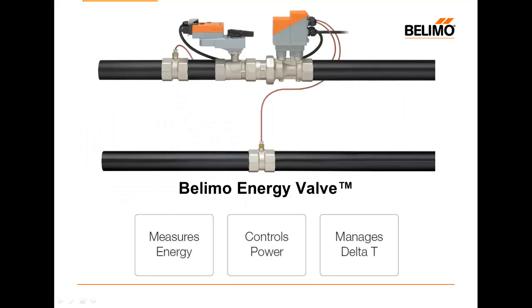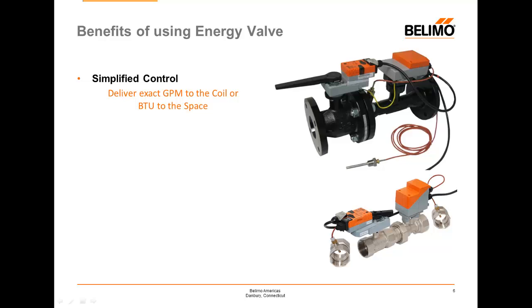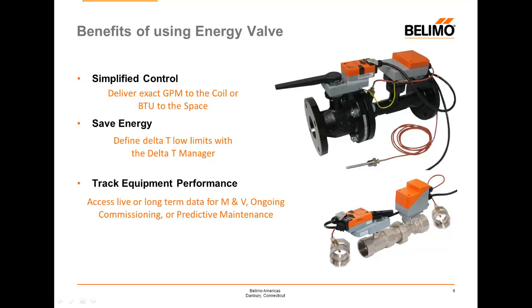Let's go ahead and talk about the Belimo energy valve. The Belimo energy valve can do several things: it measures energy, it controls power, and it manages delta T. The Belimo energy valve is a pressure independent valve with a fully integrated BTU meter. It has several benefits: we can simplify the total control strategy, deliver the exact amount of GPMs or BTUH required, save energy by using less water to satisfy the same load, and track equipment performance. The Belimo energy valve has a fully integrated onboard BTU meter and a full BACnet communication module, meaning measurement and verification can come directly from your control valve.